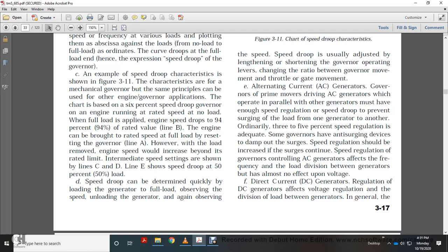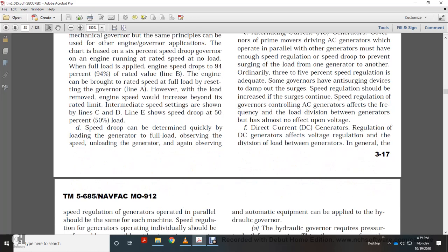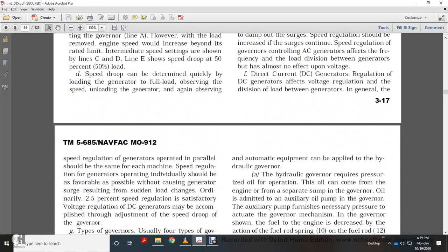Alternating current generators operating in parallel with other generators must have enough speed regulation — speed droop — to prevent surging of load from one generator to another. Ordinarily, 3–5% speed regulation is adequate. Some governors have anti-surging devices to damp out surges; speed regulation should be increased if surging continues. Speed regulation of the governor controls AC generator frequency and load division between generators, but has almost no effect on voltage.